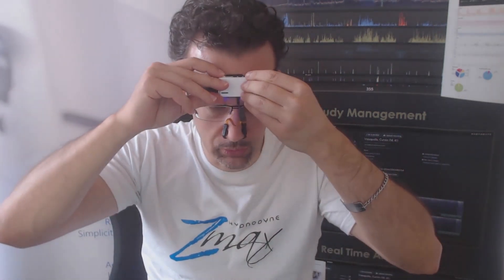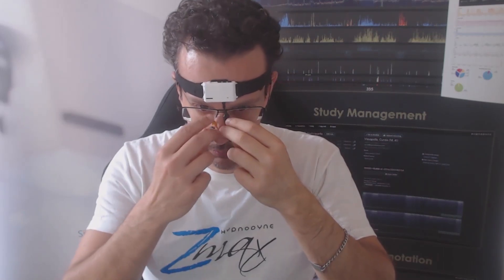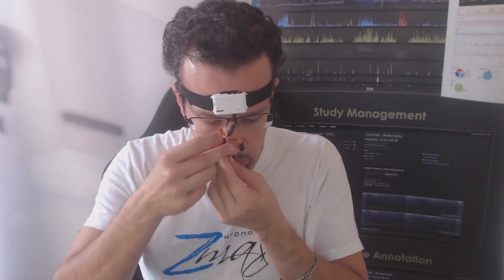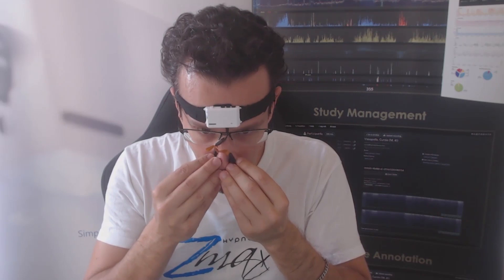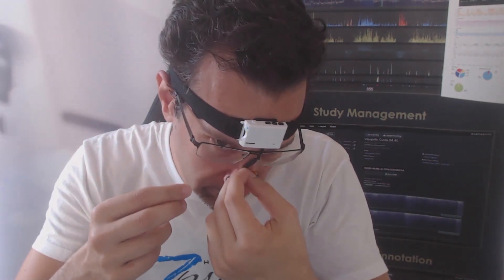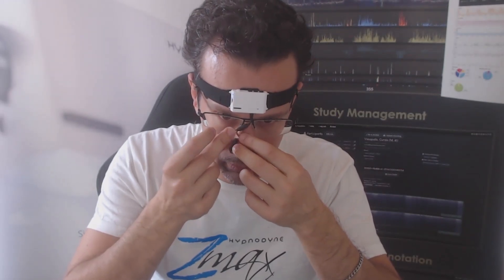When you want to actually set up a patient to sleep a whole night with it, then you might want to shorten these flat cables. That's easily done by folding them and applying a piece of tape. Once the tape is on, that's your correct size — so you don't have to do it again. You don't want to mess with it when it's on your face; you want to just simply measure, figure out by how much it needs to be shortened, and sometimes the whole thing needs to be bent about halfway through to completely shorten it. The idea is it's going to work like this, but the only problem is that to accommodate many face sizes this is a little bit longer, and so if the patient turns around in bed it's going to move the sensor — so you want to keep it as close and flat on the face as possible.